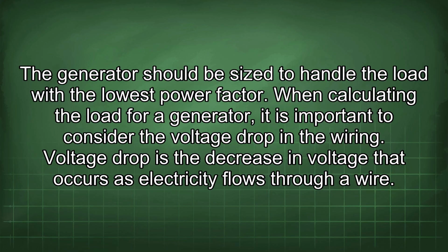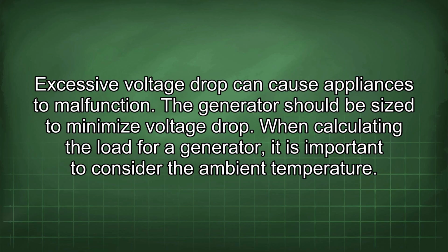When calculating the load for a generator, it is important to consider the voltage drop in the wiring. Voltage drop is a decrease in voltage that occurs as electricity flows through a wire. Excessive voltage drop can cause appliances to malfunction. The generator should be sized to minimize voltage drop.